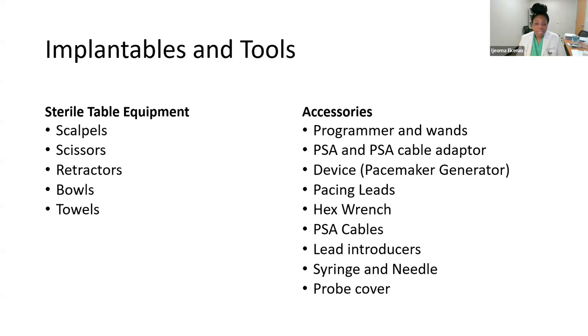Your PSA and PSA cable adapter, the PSA is your programmer, and it will help you figure out where you are and also test lead placement. The device, which is the pacemaker generator, is typically the most expensive part of all of this. And like I said, this has been a rate-limiting step, getting a pacemaker generator.